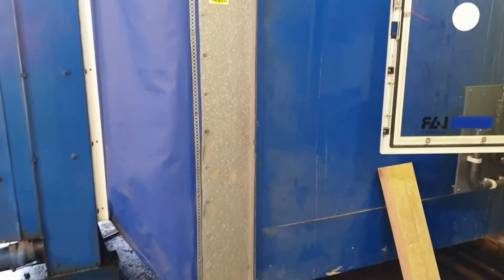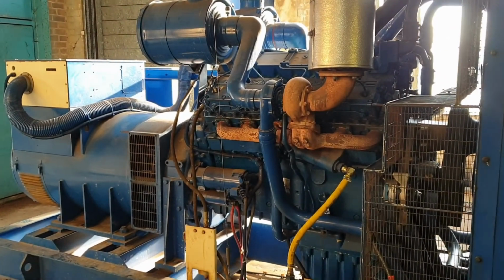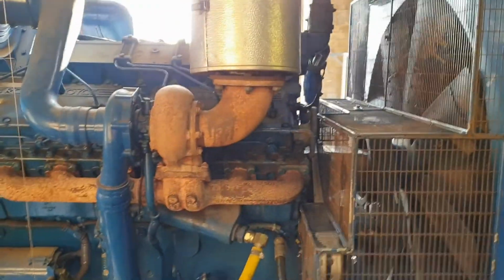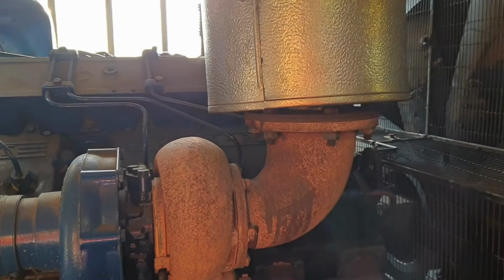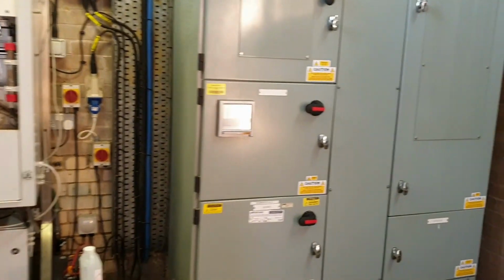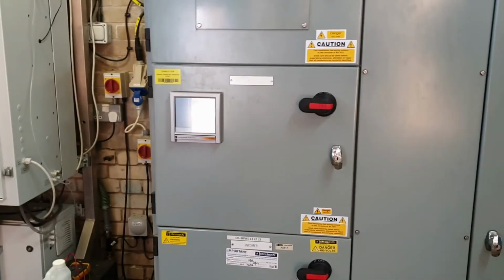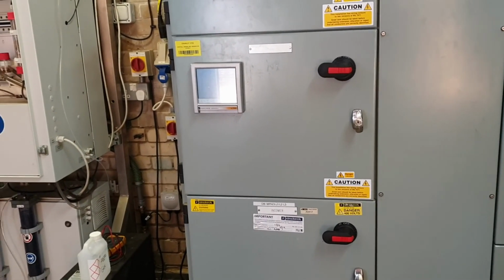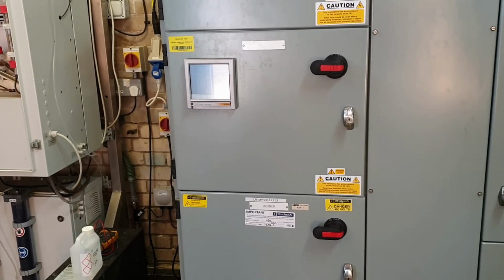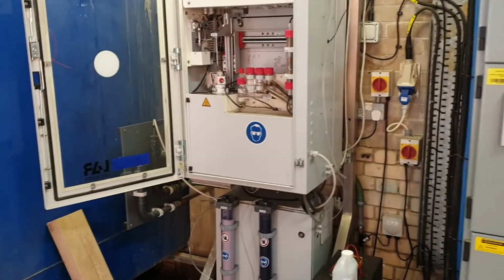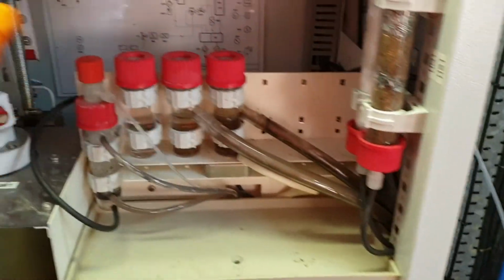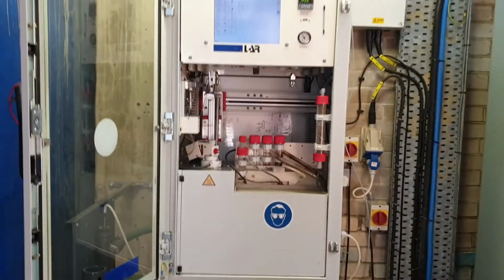Now, while we were here, that's a massive Rolls-Royce backup generator. It's really cool and awesome, and very loud when it's running. It's probably about 6 inches shorter than me. It turns out that there's a Rotork valve which adjusts the flow. The Rotork valve is broke, and it inhibits the signal from the flow meter and doesn't let the sample pump run, meaning we don't get any sample to the machine. So I've done my normal servicing things, which are seals, pump tubes, fill up the liquids, do a calibration on a known standard, which is that, and now we're just waiting for the sample pump to come back on.